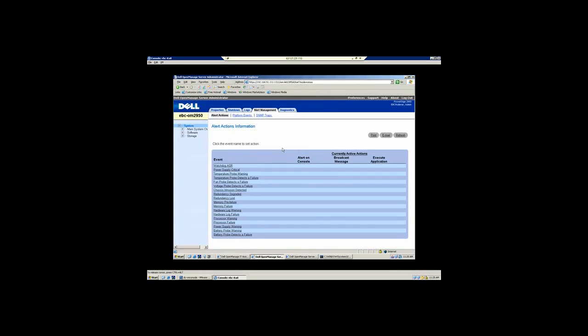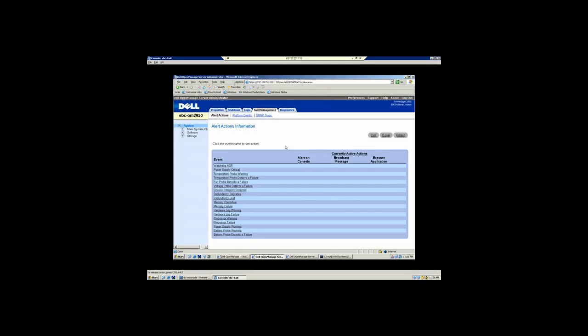Under the alert management tab you have the ability to make changes to the different types of alerts that can be generated. We set up all of that in the factory. There's no need for you to come in here and make changes. But there is the ability to come in and make chassis intrusion a non-critical thing if that's not important in your environment. So you can change it from what is now a critical alert to an information alert. Again all of this sits on a command line so you have the ability to script that configuration.